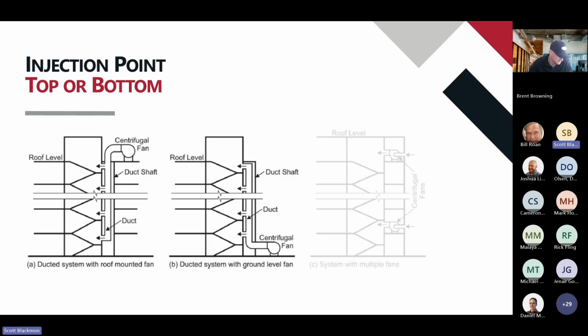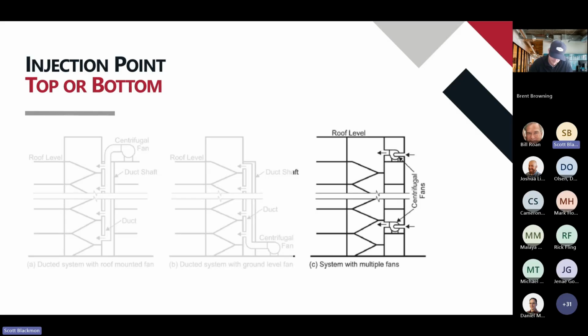When it comes to the fan location, NFPA says you can put the fan anywhere you want. You can put it on the roof, you can put it on the ground. If we're doing large buildings, say, 30, 40, 50 stories, you can actually section the fans off. So let's say you can do a 10, 12-story section and put a smaller fan there, so you're not relying on one large fan to do the entire system.